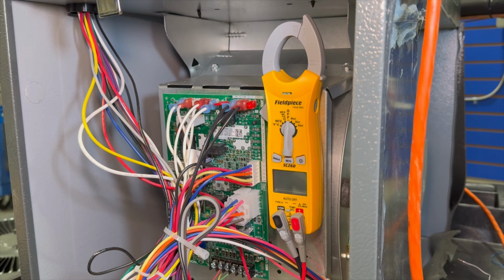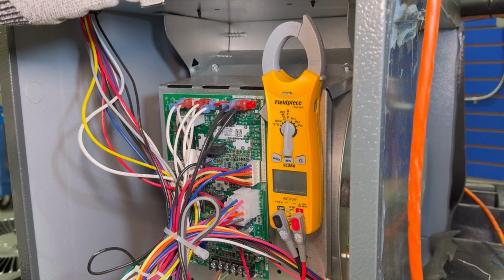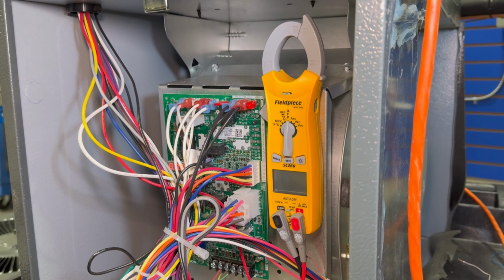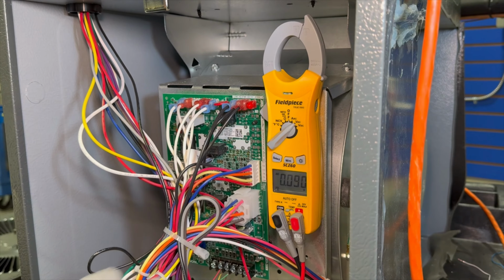So to verify whether we have 24-volt AC or DC voltage for our fan speeds, we're going to apply power to the furnace. We'll set the thermostat for a call for fan, or call for G, and then check. Let's start with AC voltage, because one common misperception is that if you don't have your full 24-volt AC — if you have a partial voltage — you must have a bad board. We're going to show that that's not really the case.